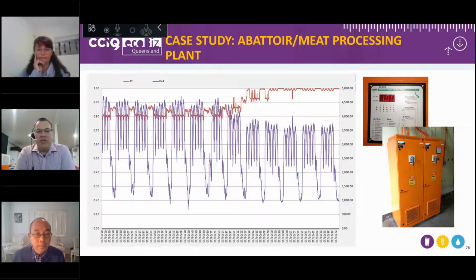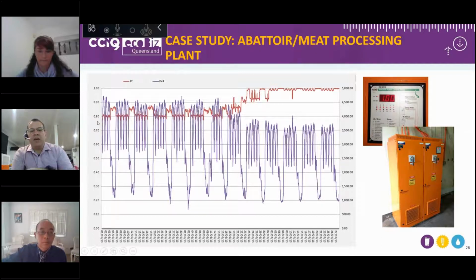Bonson, if we could flick to the next slide. Okay, so here on the slide, what we can see is that the purple line is the kVA, so the peaks and troughs of the peak demand, and the red line is their power factor. As we can see, quite a step change, and this is what power factor correction equipment does. When it's installed, you'll see the red line jumps up, and the purple line drops down. So the purple line is that immediate kVA saving that the power factor correction equipment facilitates for the customer, and the red line is the jump in the correction of the power factor. So jumping from that sort of 0.78 at peak, that really low one, through to mainly unity or close to unity after the power factor correction equipment has been installed.